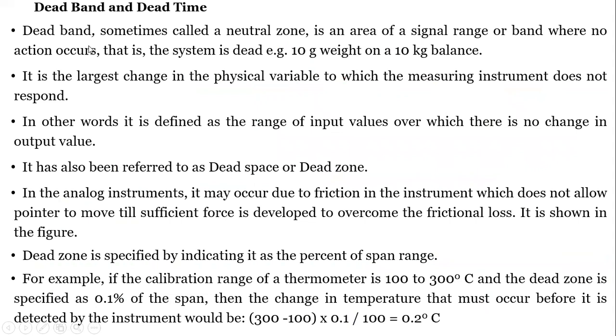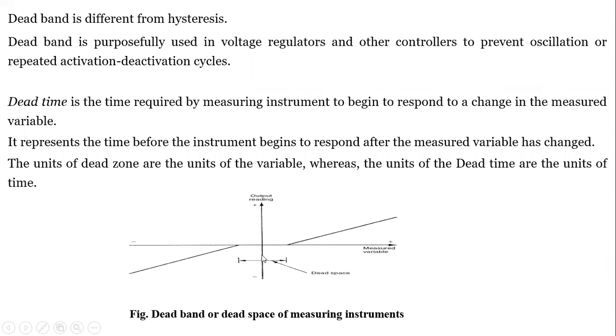Dead band and dead time are related concepts. Going from negative to positive output values, there is a range on the measured variable axis — both on the negative and positive sides — where the instrument will not respond; this is the dead space or dead band. Dead band is purposefully used in voltage regulators and controllers to prevent oscillation or repeated activation. Dead time is the time required by the measuring instrument to begin to respond to a change in the measured variable.